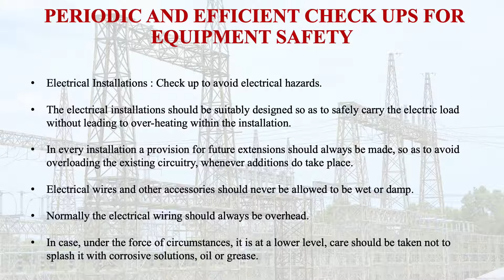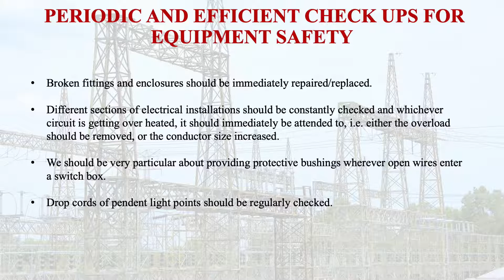Broken fittings and enclosures should be immediately repaired or replaced. The replacing of these broken fittings is required for electrical safety. Different sections of the electrical installation should be constantly checked, and whichever circuit is getting overheated should immediately be attended to. Either the overload should be removed or the conductor size should be increased so that it can accommodate the current, but it is generally preferred that the overload should be removed. We should be very particular about providing protective bushings whenever open wires enter a switch box. Then drop cords of pendant light points should be regularly checked in the electrical installations.